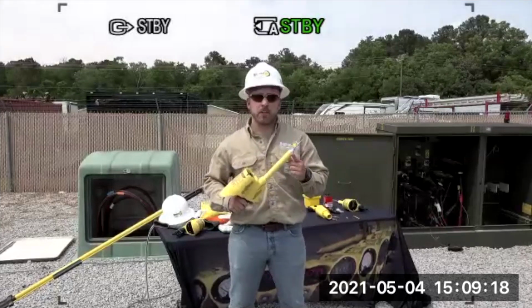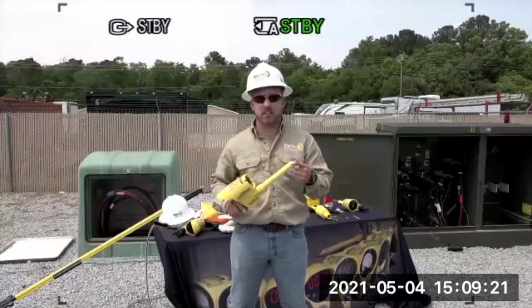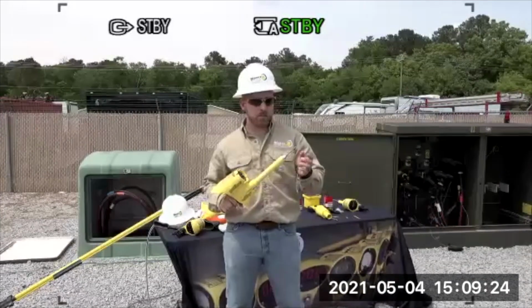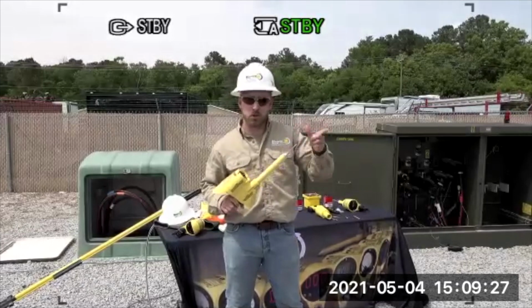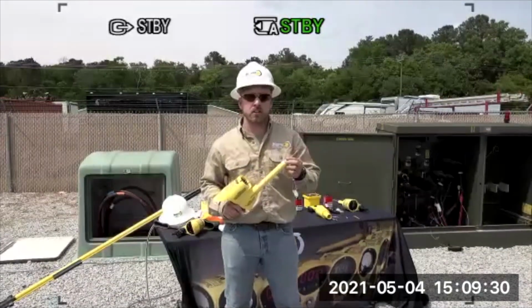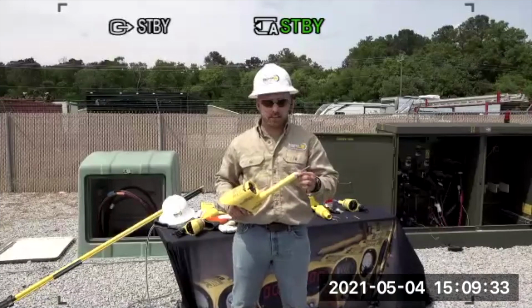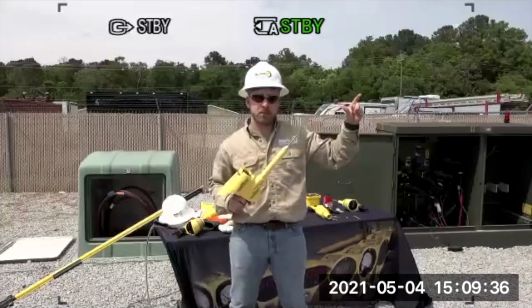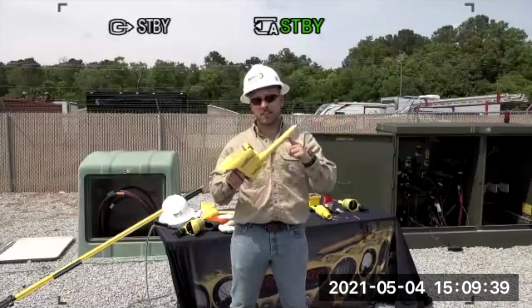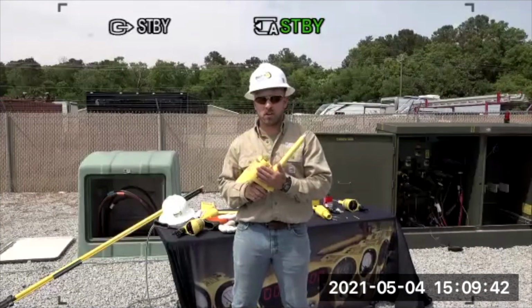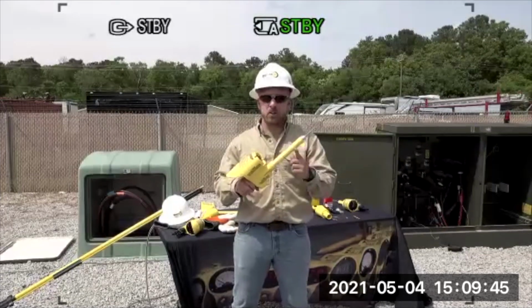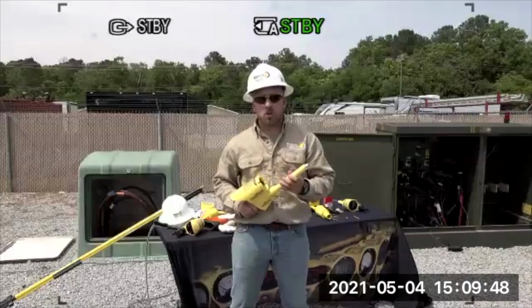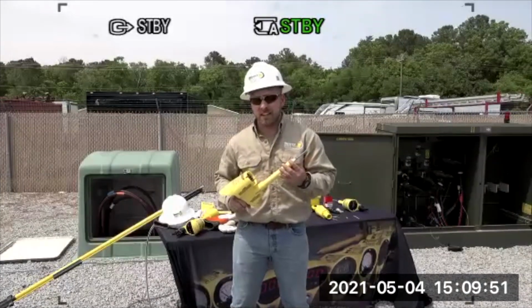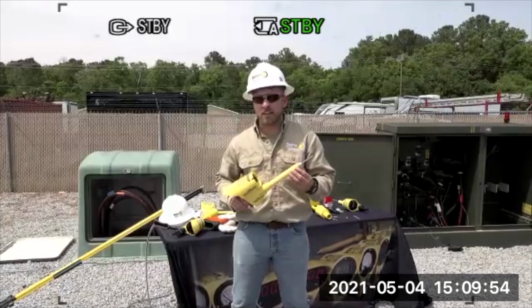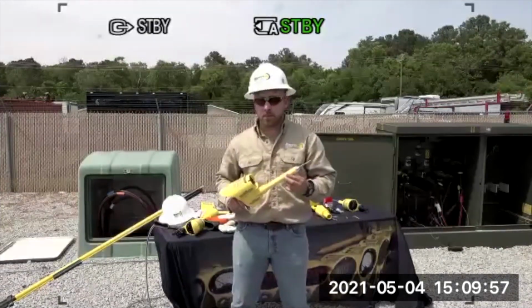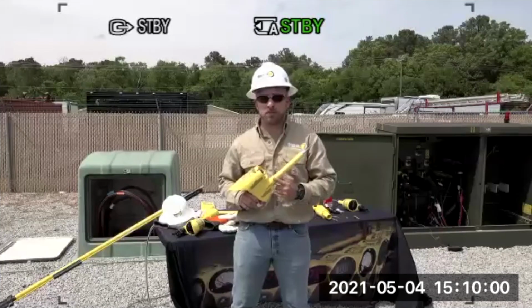That's also the reason why you always want to use the proper accessory and take no shortcuts - it could be a hook probe, a straight probe like we have here, or a bushing adapter. That extends your depth perception so you don't cross that line, because the components inside these meters are conductive, and once you cross that line you could potentially have a flashover. Also, always keep the probes clean with no calibration stickers or writing, so you prevent any kind of flashover.